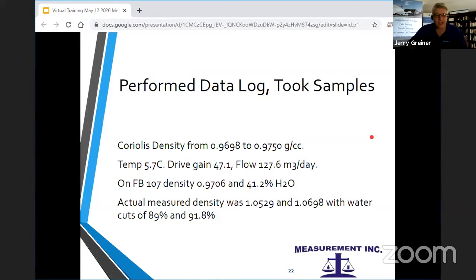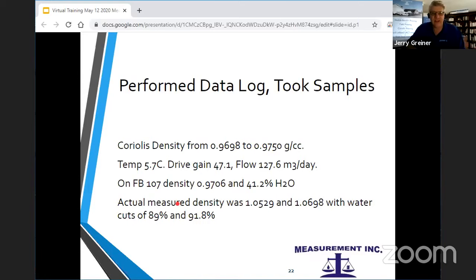And what we found during data log is the Coriolis would show like a density 0.96, 0.97 kind of density. The temperature was 5.7, the drive gain 47, which is really high. This is a pumped liquid meter. Usually a drive gain is like very low, under 10%. The flow rate was a decent flow rate on this pumped meter. On the FlowBoss, we found the same numbers. So the numbers calculated out what they should be on the FlowBoss. And our measured density was actually 1.05, 1.06, and water cut should have been like in the 90% range, not the 40% range.